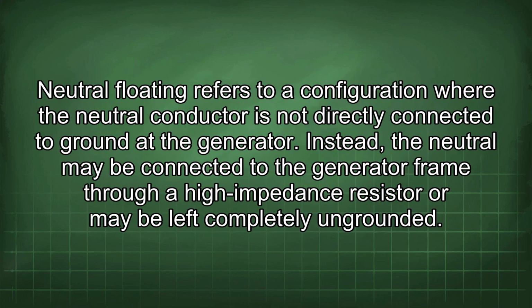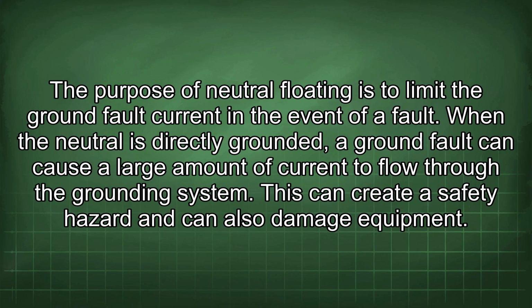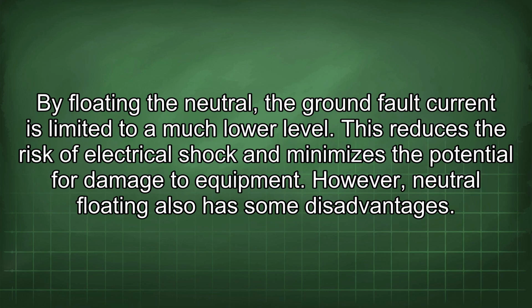Neutral floating refers to a configuration where the neutral conductor is not directly connected to ground at the generator. Instead, the neutral may be connected to the generator frame through a high-impedance resistor or may be left completely ungrounded. The purpose of neutral floating is to limit the ground fault current in the event of a fault. When the neutral is directly grounded, a ground fault can cause a large amount of current to flow through the grounding system. This can create a safety hazard and can also damage equipment. By floating the neutral, the ground fault current is limited to a much lower level. This reduces the risk of electrical shock and minimizes the potential for damaged equipment.